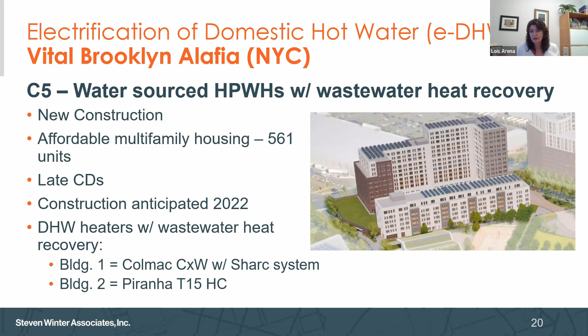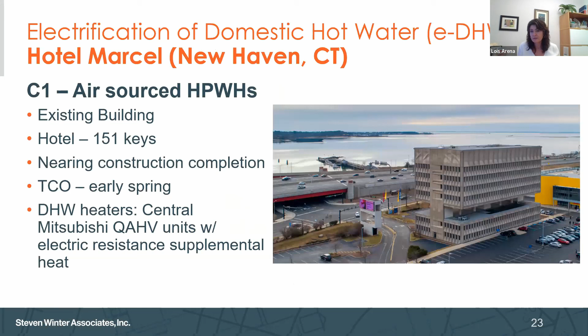Well, as Dylan mentioned, space is 100% an issue, especially if they're trying to change both heating and domestic hot water systems over, where are they going to put all those condensing units if they don't have a podium roof as well? So space is a huge consideration, because you also need more storage than you would if going from a gas system to an air-to-water heat pump. You need a lot of storage so your spikes aren't too great when the peak load is happening in the building.